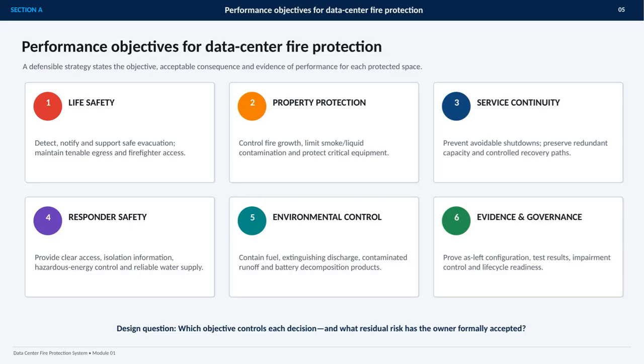A defensible data center fire protection strategy begins by defining the objective for each protected space, the consequence that is acceptable, and the evidence that demonstrates performance. The goal is not simply to install fire protection, but to make each decision traceable and supportable. The first objective is life safety: detect and notify occupants, maintain tenable egress, and support firefighter access. Second is property protection, which means controlling fire growth, limiting smoke and liquid contamination, and protecting critical equipment.